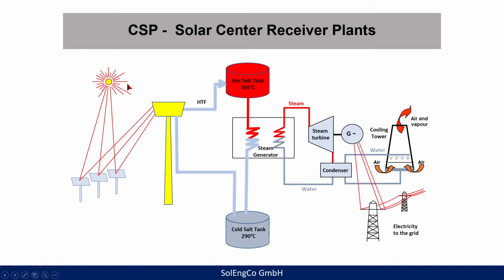After sunset, or when solar irradiation is insufficient, this part of the loop closes—the pumping from the cold tank through the receiver. However, pumping from the hot tank through the heat exchangers can continue until the hot tank is empty, ensuring operation without sun whenever we need to generate power. This technology is commercially proven; up to now about 4 gigawatts of CSP plants with molten salt thermal energy storage have been implemented worldwide.